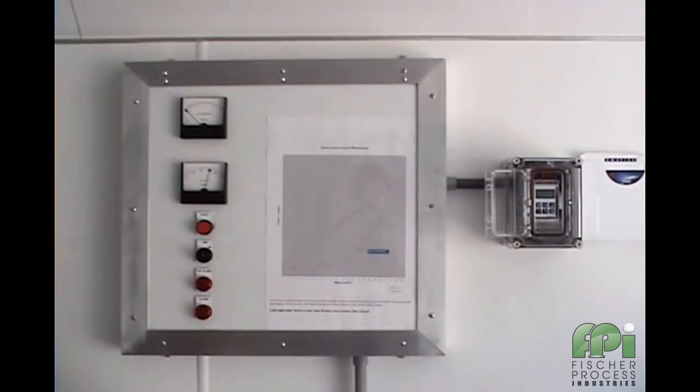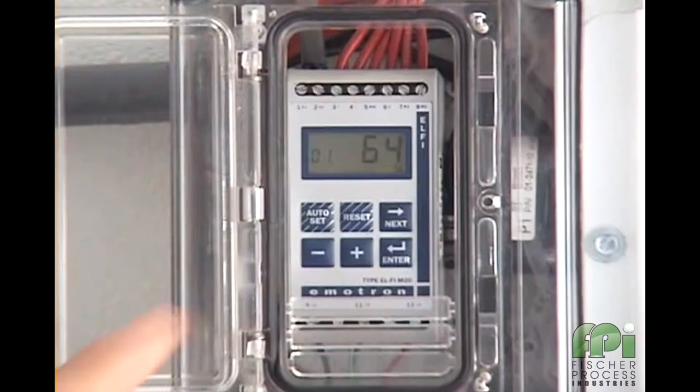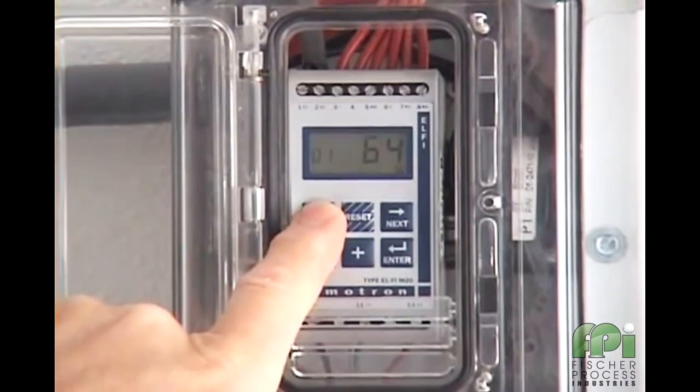Next we will teach the M20 what the normal load is and at the same time establish four levels of protection — two for overload and two for under load. All of this is achieved by simply pressing the auto set button for three seconds, a unique and patented feature only found on the Emotron load monitor.